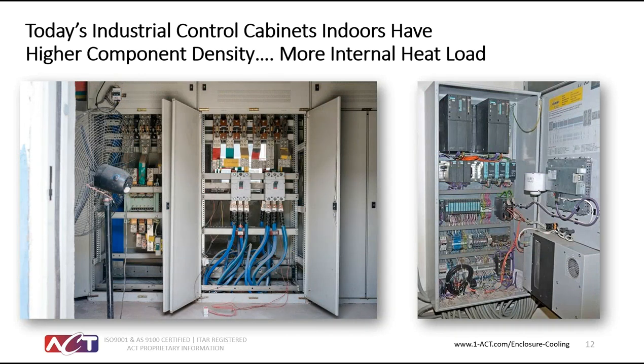So in today's industrial cabinets, you have a higher component density, which we're all used to. The things are getting smaller and smaller, but also the packages become hotter and hotter. And so as you see applications like this where a door is open, it's not only a hazard, arc hazard for shock, but it's no real way to cool the electronics within that cabinet.